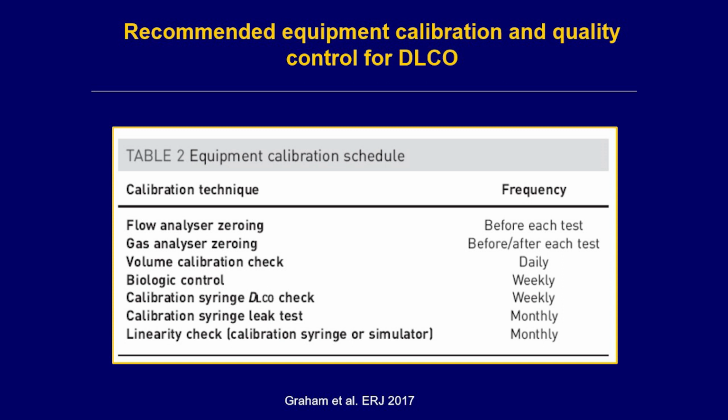The volume should be checked. There should be biological controls. You should calibrate the syringe, and you could calibrate the syringe leak test, and you should check the linearity. I'm sure that you and your technicians are not very much interested to do this.